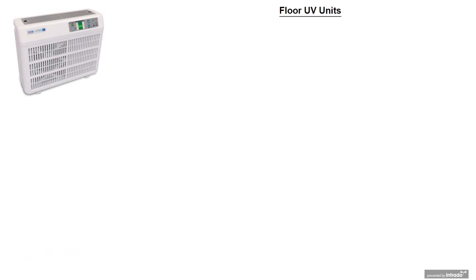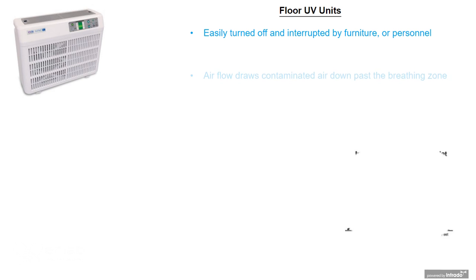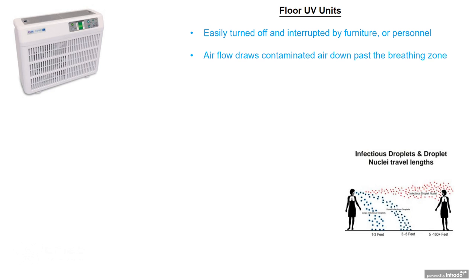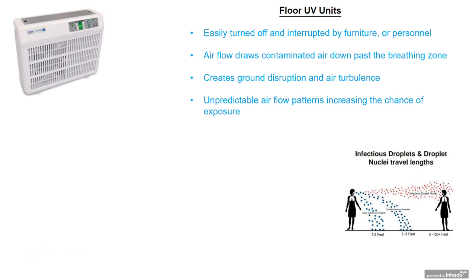And floor UV units. So yes, there's a lot of different technologies out there, I understand, but that's what's available, and I just want to make sure we educate on all of these different technologies. So these floor UV units, again, can be easily turned off and interrupted by furniture or personnel, just like a floor filtered unit. The airflow draws contaminated air down past the breathing zone. It creates ground turbulence and inadequate distribution and very unpredictable airflow patterns.